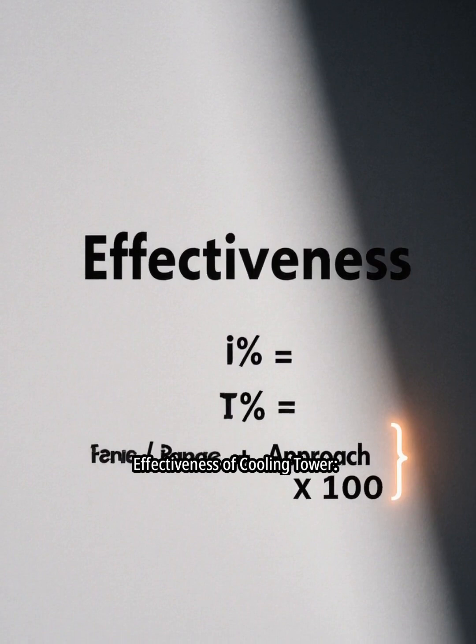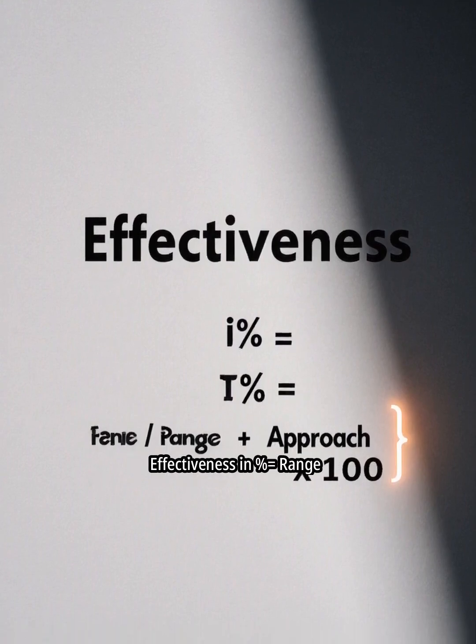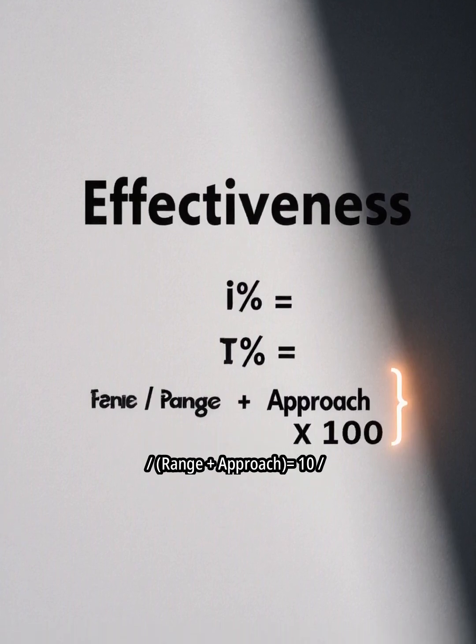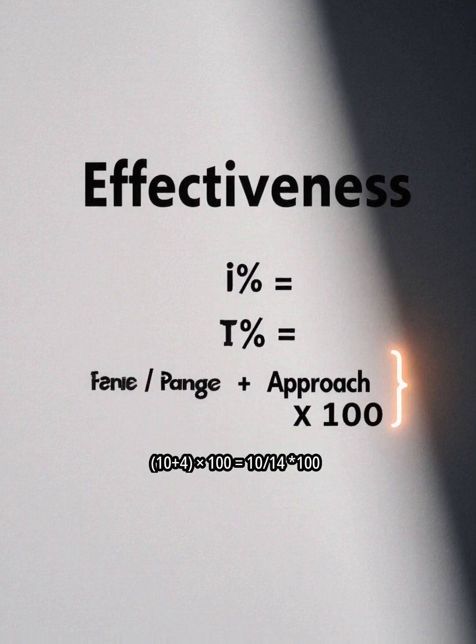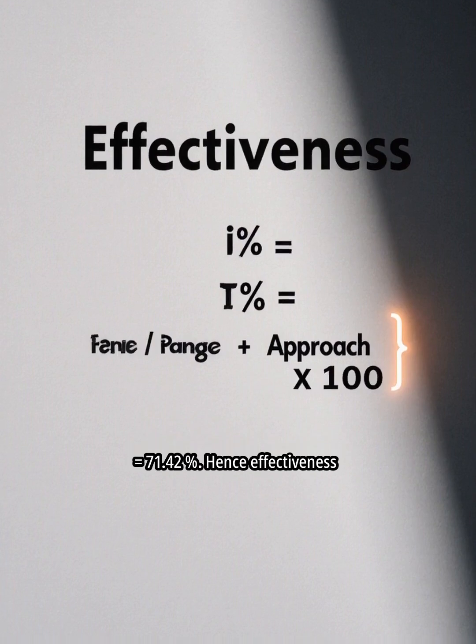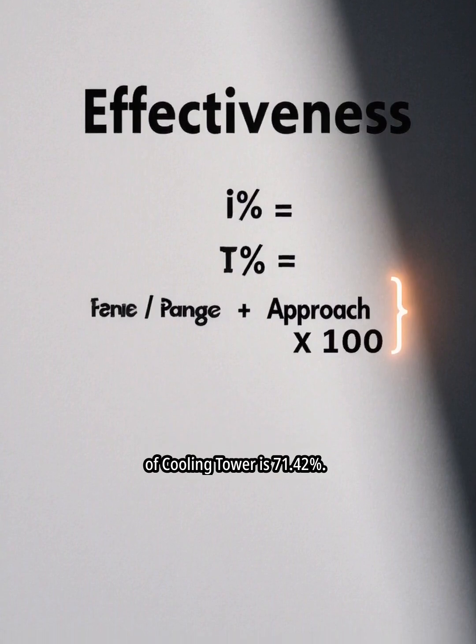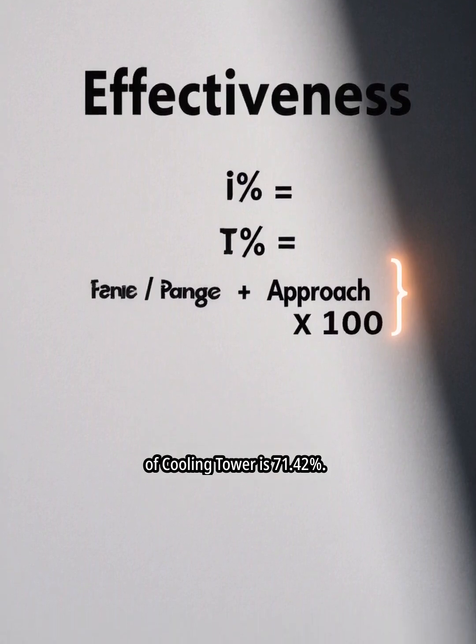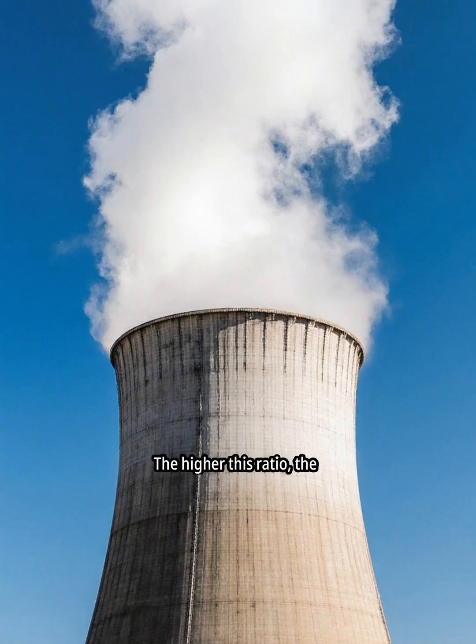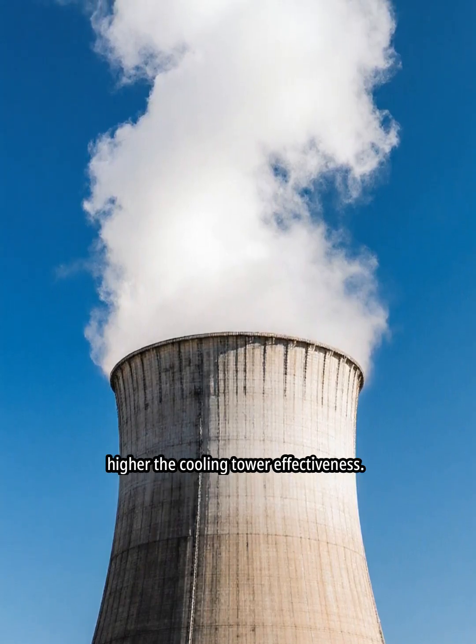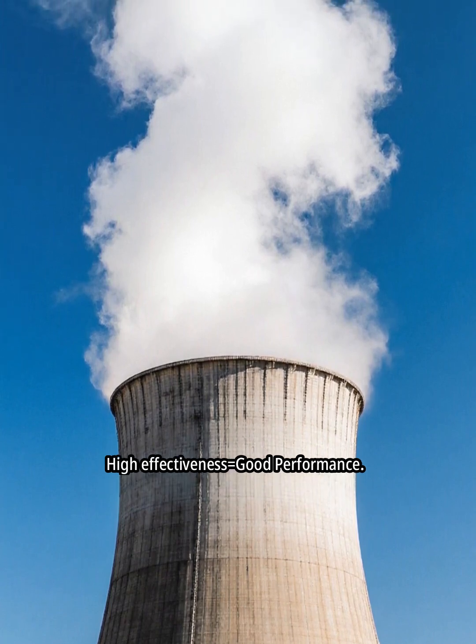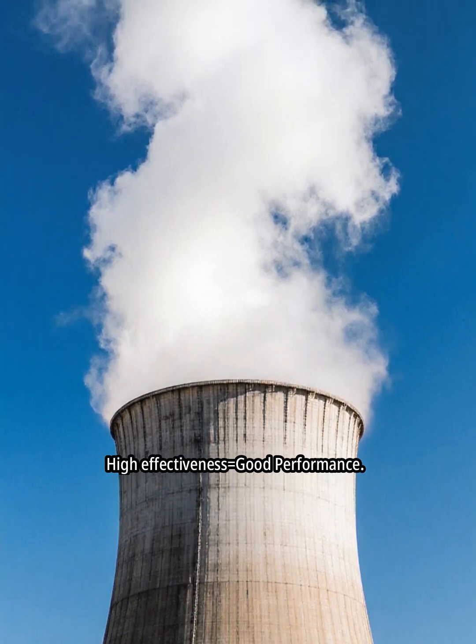Effectiveness of cooling tower. Effectiveness in percent equals range divided by range plus approach, equals 10 divided by 10 plus 4, times 100, equals 10 divided by 14 times 100 equals 71.42%. Hence, effectiveness of cooling tower is 71.42%. The higher this ratio, the higher the cooling tower effectiveness. High effectiveness equals good performance.